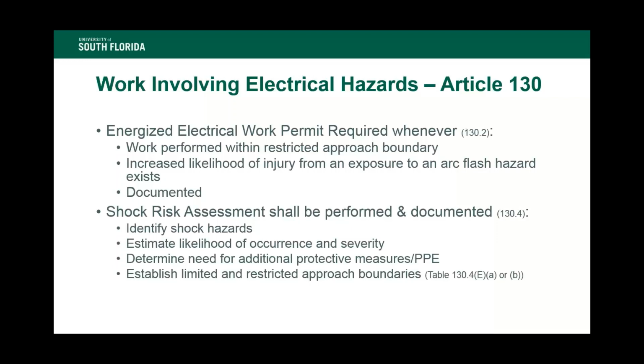It's also required that the employer conduct a shock risk assessment, and that assessment also be documented. The assessment is to identify the shock hazards. It's also to estimate the likelihood of occurrence of an electrical shock and the potential severity of that shock. It's also used to determine the need for additional protective measures, such as personal protective equipment. It's also used to establish limited and restricted approach boundaries so that we don't get people tangled up with live electrical equipment, okay? And oftentimes, these limited and restricted approach boundaries can be based on the table in 130, and that's Table 130.4(E)(a), which is for AC circuits, or (b) for DC circuits.